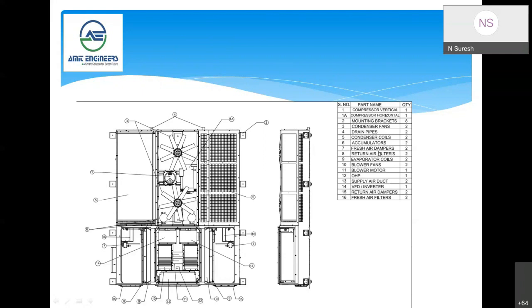Point number 7 is the fresh air dampers. Why are fresh air dampers required? Since there are around 78 passengers inside the coach, to keep the oxygen level and to dilute the carbon dioxide level, two fresh air dampers are provided. The air volume and air quantity are calculated as per international standards. One unit will produce approximately 700 cmh, so that fresh air will be fed into the system continuously. We'll explain each component in more detail in the coming slides.